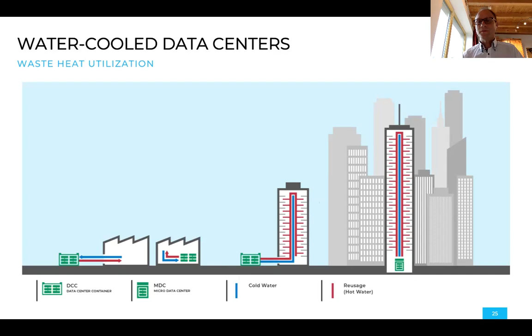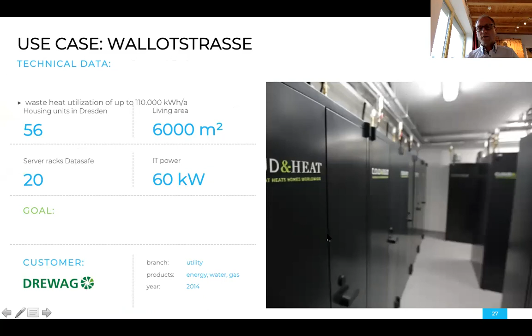This is an apartment building built five years ago, with 56 apartments. In the cellar, we placed our servers with our heat recovery technology—you can see the piping here, all liquid piping. We need very little air; the rest is direct water cooling. The 56 apartments are basically heated with the waste heat from these servers, which we did together with a local energy provider.